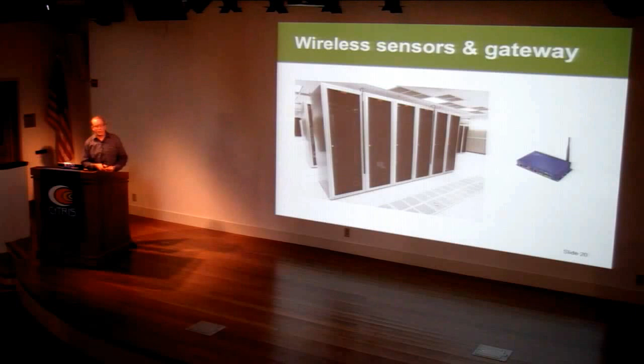The effect of having this system, which allows us to rapidly deploy many sensors, gives us and our customers a lot of visibility about what's going on in their data center. They're not left with just 1, 2, or 5 temperature monitoring points to alarm on. Now they can have hundreds of temperature sensors all over the place, put in just the right spot to measure the temperature of the cooling fluid for the servers, which is the air temperature being drawn in at the front of those racks.